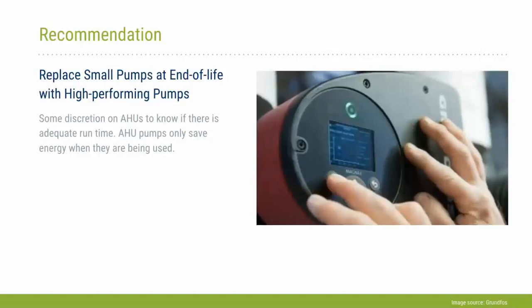So the overall recommendation at this point is evaluating these when we are replacing those smaller pumps at end of life, and looking at those runtime hours. In most of these applications, we had the pumps scheduled on with the BAS already, so we're only seeing those savings during operating hours, but we are seeing increased control that we weren't getting prior to installing these pumps. In the case of the air handlers, because it was internal load and they were secondary pumps, we found that the main hot water pumps from the building were able to meet a lot of that load. So it's about evaluating the existing conditions to make sure we are getting adequate runtime from the pumps when we are evaluating these opportunities.